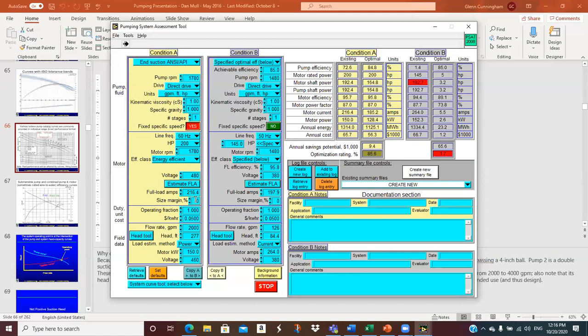Operating fraction, that's the fraction of a year in terms of hours. If this thing operates continuously, I put in 8760 hours per year. If it operates 2,000 hours a year, you take 2,000 divided by 8760, and whatever that fraction is, you put it in there. The next is the dollars per kilowatt hour. Right now, it defaults to 5 cents a kilowatt hour. If it was 10 cents, you'd put in 0.1. It does not do consumption and demand separately. That is a potential criticism. You get a better analysis if you separate the demand and the consumption, but that's not designed into this.